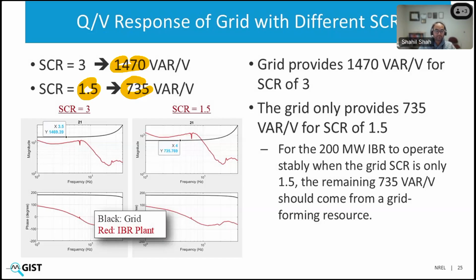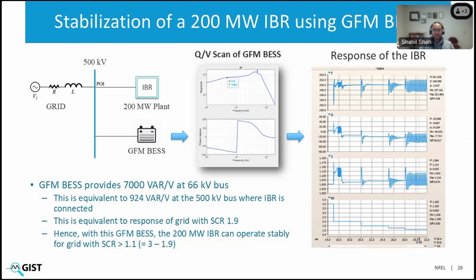So we took one IBR model, a grid forming BESS model, and performed its Q by V scan. And then we found out that the BESS is providing approximately 7,000 var per volt at its POI, and that is connected to a 66 kV bus. Now, if it is providing 7,000 var per volt at the 66 kV bus, because the POI of our IBR which we are trying to stabilize is at 500 kV, the response from this grid forming BESS would be 924 var per volt.